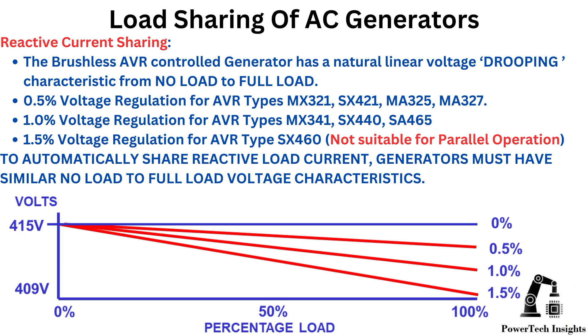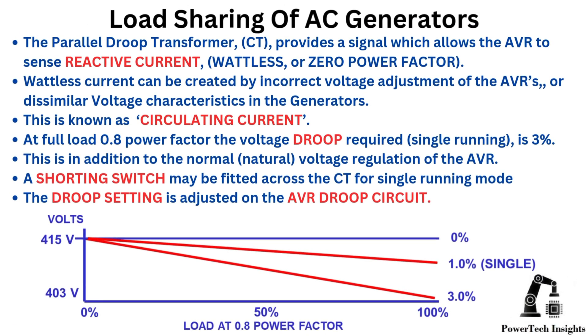To automatically share reactive load current, generators must have similar no-load to full-load voltage characteristics. The parallel droop transformer (CT) provides a signal which allows the AVR to sense reactive current (wattless, or zero power factor). Wattless current can be created by incorrect voltage adjustment of the AVRs or dissimilar voltage characteristics in the generators — this is known as circulating current. At full load, 0.8 power factor, the voltage droop required for a single running generator is 3%, in addition to the normal natural voltage regulation of the AVR. A shorting switch may be fitted across the CT for single running mode, and the droop setting is adjusted on the AVR droop circuit.